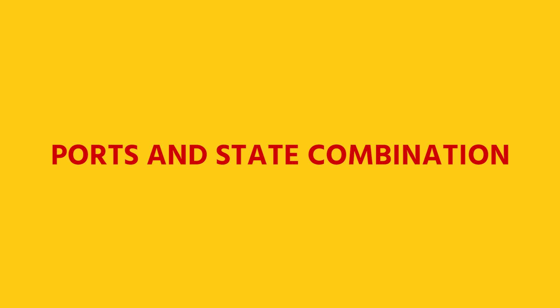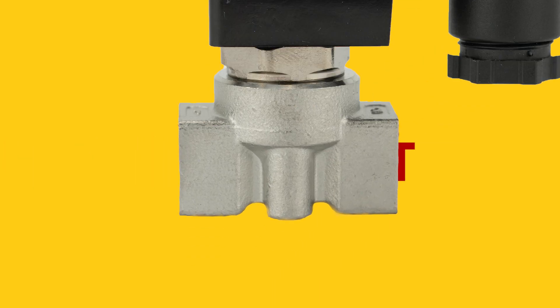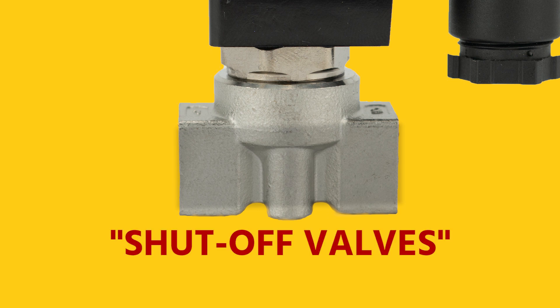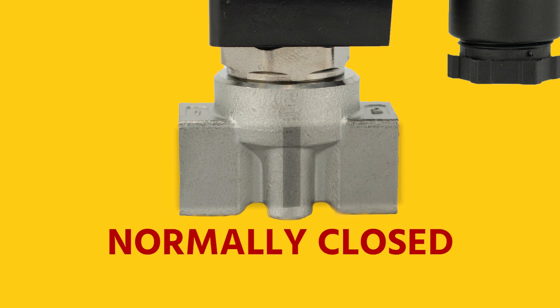Selecting the correct port and state combination can be hard, so let me explain the four most common used pneumatic solenoid valves. A two/two-way valve has two ports — in and out — and it has two states: open and closed. Two/two-way valves are therefore often called shut-off valves. They can be normally open or normally closed.